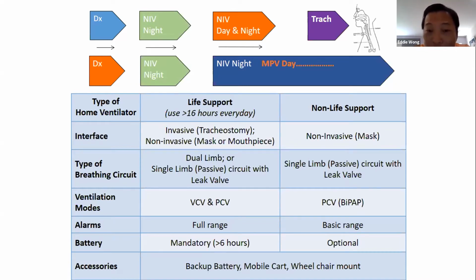Okay, when we come to the monitored parameters and alarms, I will show you 4 parameters to monitor, which relate to the alarm settings. From there, you will understand that even though this is a basic range, you are safe, you are well protected, even though the alarm is a basic range for the non-life support ventilator.